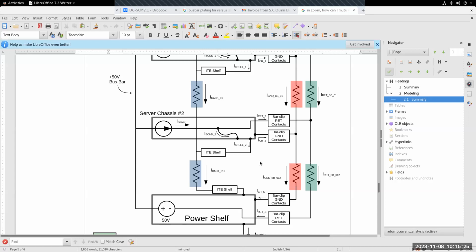I was trying to visualize the actual fault that was being anticipated here, and I haven't really figured it out. The only thing I could discern was, if I have a 30 amp whip, then each of the 3 phases of my Y whip is breakered at 30 amps. Is that where the 64 amps comes from, which is twice that for 2 minutes? I don't know. What is the fault that's anticipated? We don't have to talk about this, but this is a question that I had.